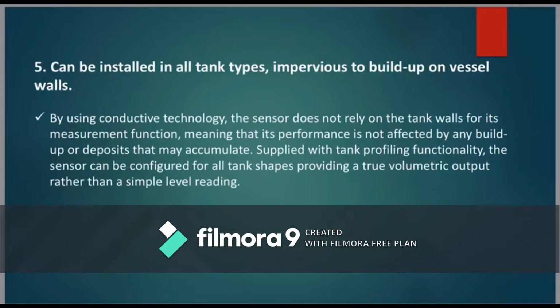And the last one, the fifth one, can be installed in all tank types, impervious to build up on vessel wall. By using conductive technology, the sensor does not rely on the tank walls for its measurement function, meaning that its performance is not affected by any build-up or deposit that may accumulate. Supplied with tank profiling functionality, the sensor can be configured for all tank shapes, providing a true volumetric output rather than a simple level reading. This means that the sensors can be easily installed anywhere, that easy for the sensor to scan the water level.